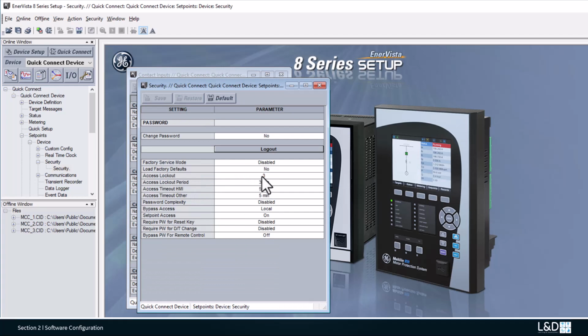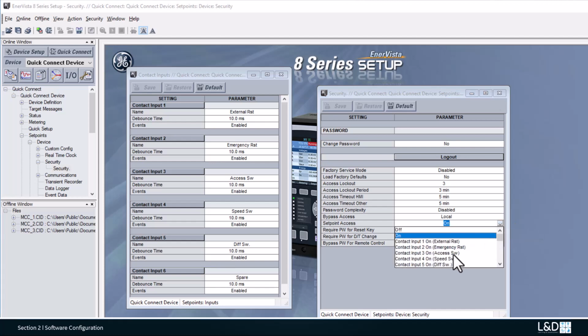So for example, the external reset, emergency start, access switch, speed, differential, and spare, etc. To use these default names, the relevant setting needs to be configured. For example, for the access switch, we need to go to the security settings and configure the access points. For this case, we can choose access point 3 and save. Another example is the 52A switch contact. 52A is under the breaker, and for this one we need to first configure the switching device to be the breaker.